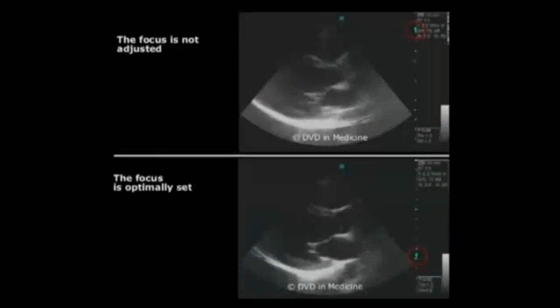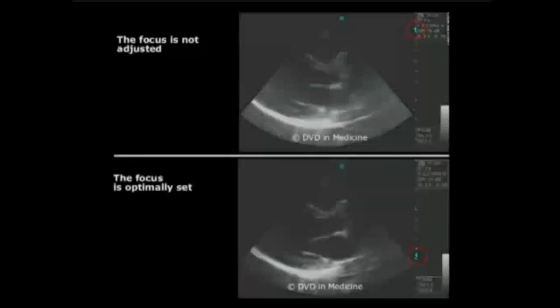Now, on the divided screen, you can see the direct comparison of two real-time images taken from the same patient. On the upper image, the focus is not adjusted, and on the lower image, the focus is optimally set. The optimal level of compression. The compression setting can considerably impact the two-dimensional image quality.